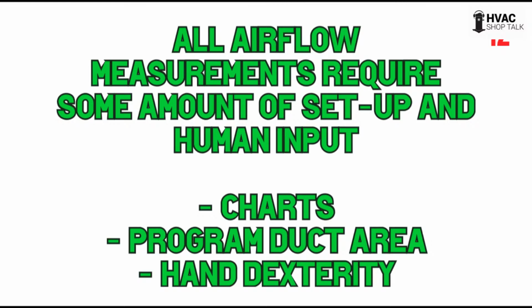Measurements require some amount of setup and human input. Human input means opportunities for mistakes and wrong readings. You may have to go to a chart, go to your chart for your static pressure, and make sure it's the right blower because there are several steps there. You've got to pay attention to that stuff.